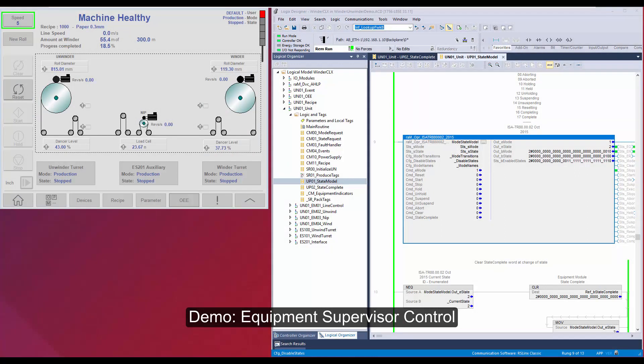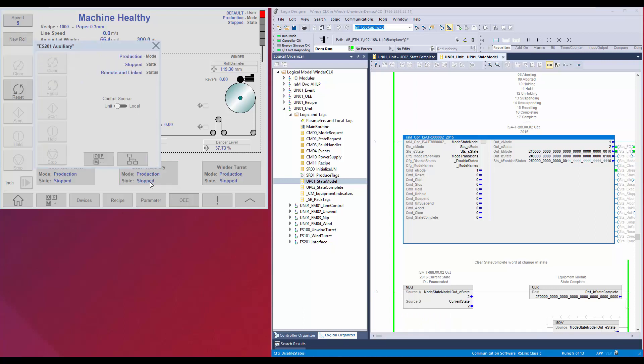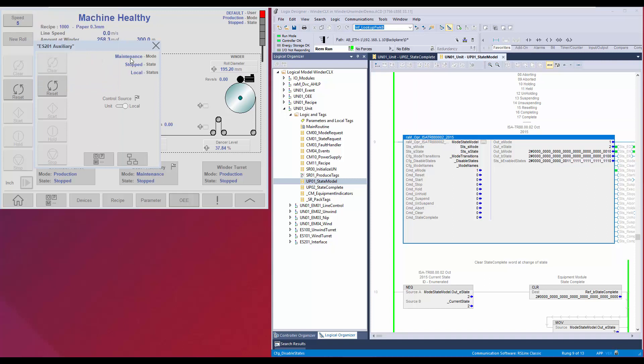Next I will show how equipment supervisor can be selected as local control and unit control. I will open the auxiliary equipment supervisor faceplate. Currently the control source is under unit. I will switch to local control. Now the state command buttons are enabled. I will press reset and start. You can notice, though the machine is under stop state, the auxiliary supervisor is in running state. I will press the stop button. It is also possible to change the modes in equipment supervisor while in local control. Now you can see the equipment supervisor is in maintenance mode while the unit is in production mode. This gives freedom to the operator to operate the equipment under the supervisor independently or in sync with the unit. All this is done without disturbing the unit state model or modifying the code.